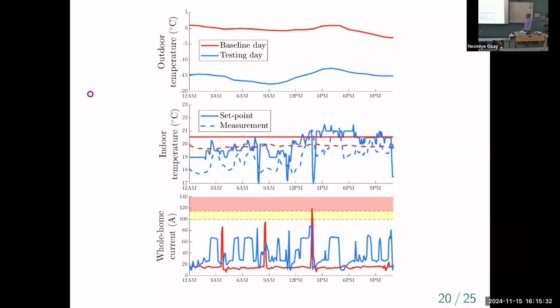And basically what's happening there is that there is defrost needed. So again, ice is built up on the outdoor unit and the manufacturer controls want to basically turn on the resistance heating element and switch the direction of refrigerant flow, which uses a ton of power. So basically to make room for that, we turn down the amount of heat that we're asking for. So that's what these large drops are here. And the bottom plot here, rather than power, I'm plotting the whole home current. So this is not just the devices that we're controlling, the heater and the water heater, but it's also everything else in the house. And you can see that while the baseline control sometimes gets up around 120 amps for our house, on this day at least, we maintained the house below about 90 amps.